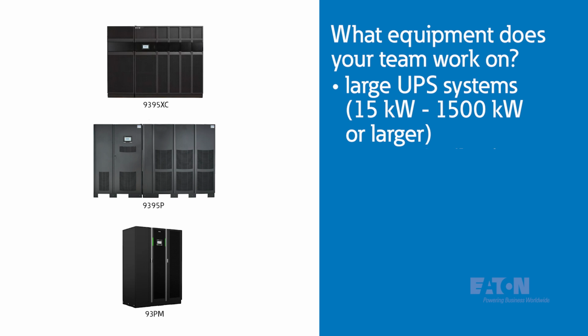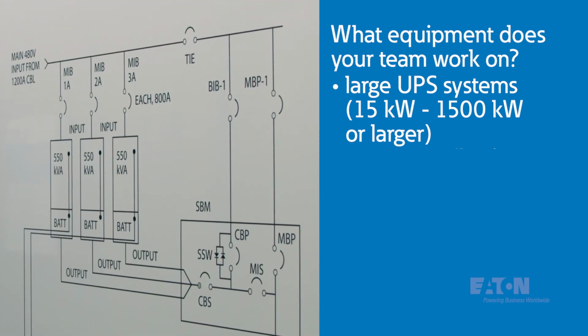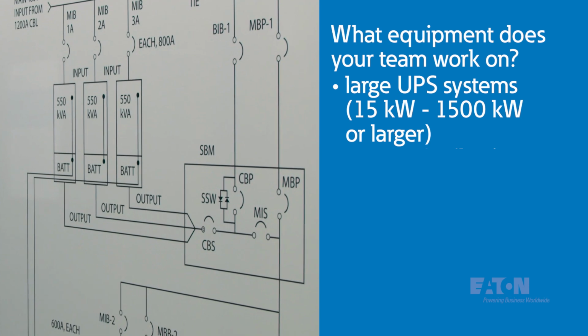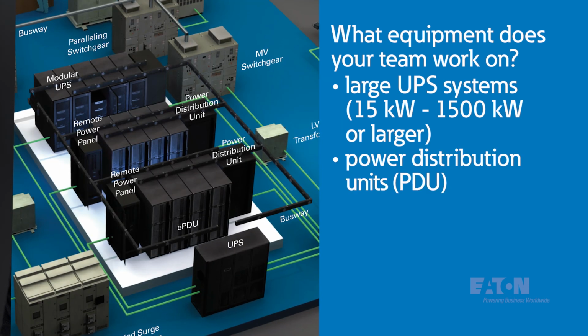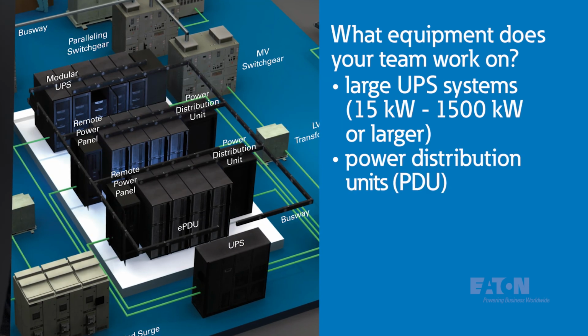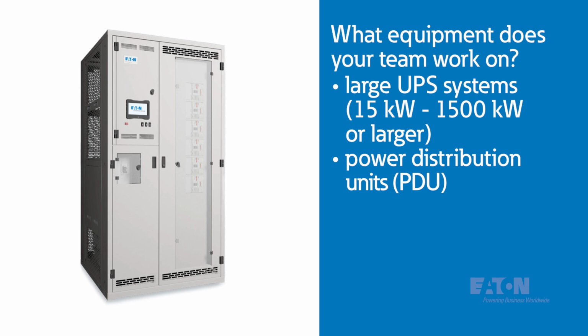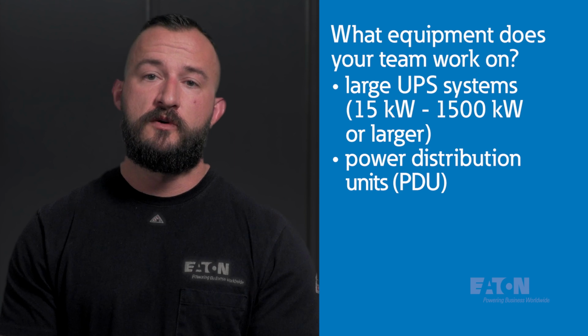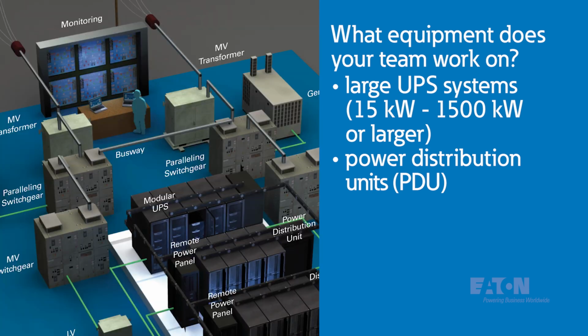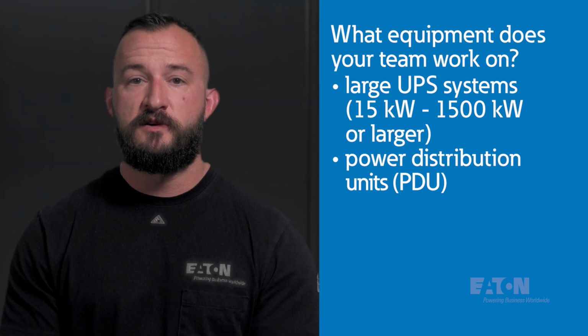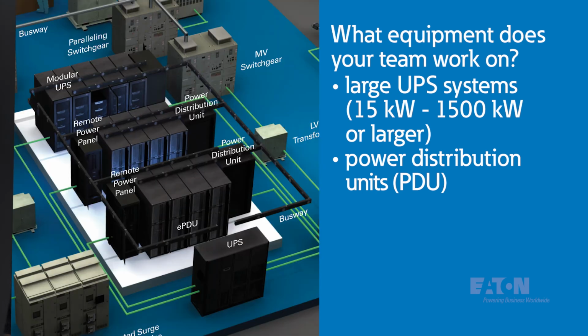UPS with modular parallel systems can be much bigger. Some of our customer systems have more than 100 megawatts of UPSs. It also includes power distribution units, or PDUs. These are simply a transformer and a panel board, or multiple panel boards, in a single enclosure. With larger subfeed breakers, they can feed busway or remote power panels. PDUs with miniature breakers feed EPDUs and racks, which in return feed the servers.